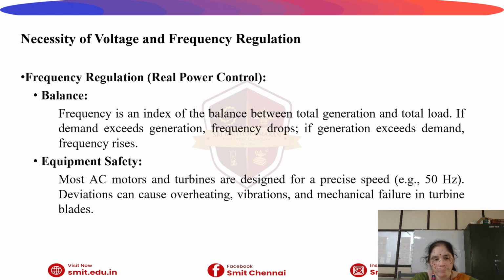Similarly, we can control the voltage using the reactive power. In general, real power controls the frequency and reactive power controls the voltage. Now if we focus on frequency regulation, that is the real power control, the balancing of the two powers, generation and load, is very important. Frequency is an index of the balance between the total power generation and the total load. If the demand exceeds generation, frequency drops, and if generation exceeds the demand, frequency rises.